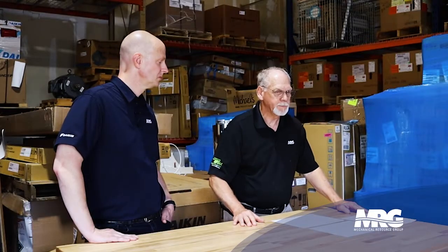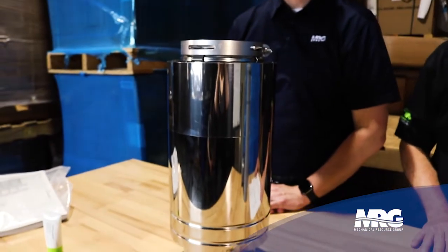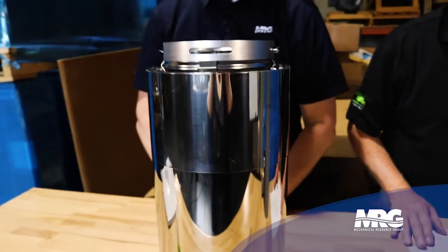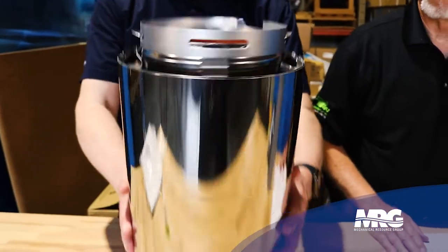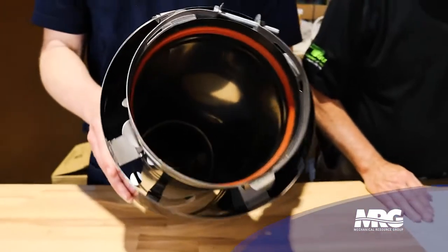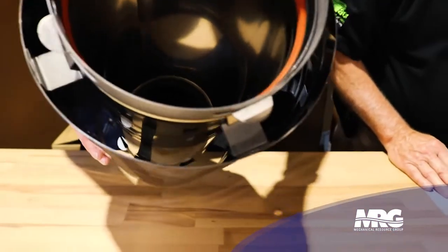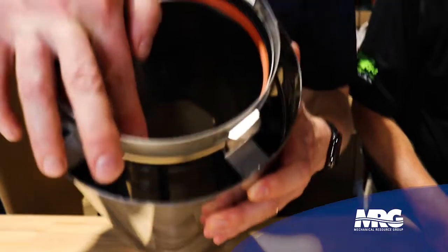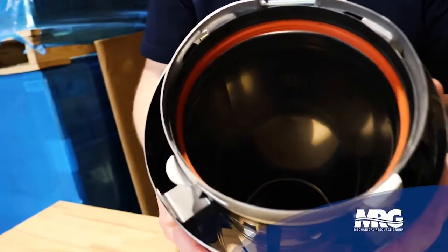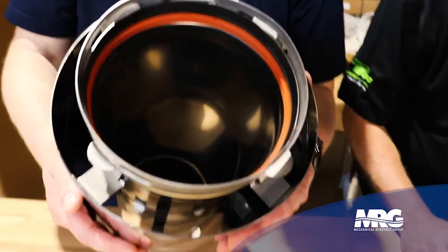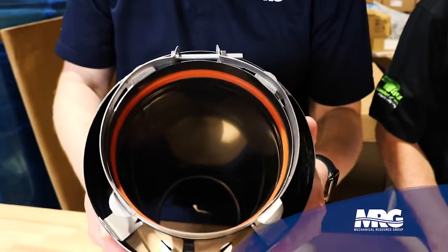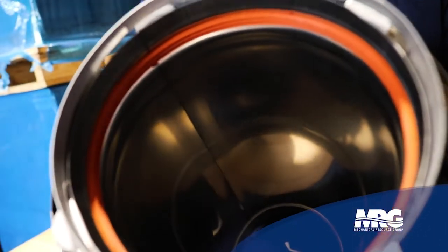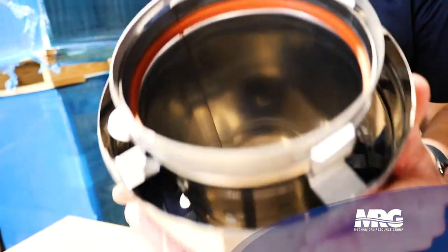In that condition. On the Category 2 duct, this is the stainless steel double wall, and AL29-4C is the classification of that. It is double wall. It is 304 stainless inner pipe, and it has a 3/16 cover on the outside so that it looks nice. And that's what we use on the venting in the Category 2 for the low temp.